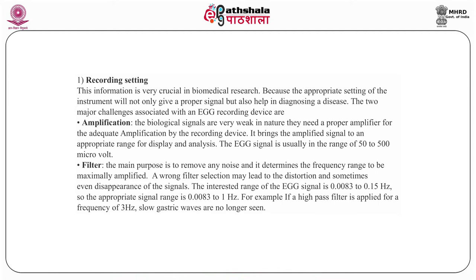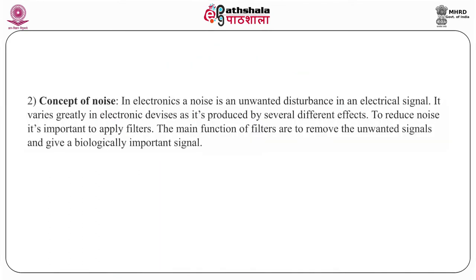The appropriate signal recording range is 0.0083 to 1 Hz. For example, if a high-pass filter is applied at a frequency of 3 Hz, slow gastric waves are no longer seen. In electronics, noise is an unwanted disturbance in any electrical signal. It varies greatly in electronic devices as it is produced by several different effects. To reduce noise, it is important to apply filters, whose main functions are to remove the unwanted signal and retain only the biologically important signal.